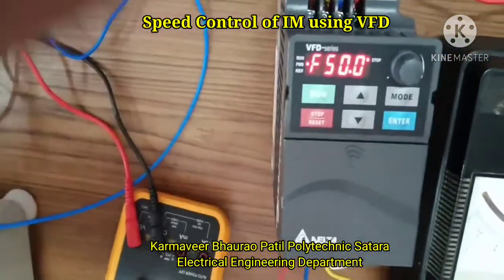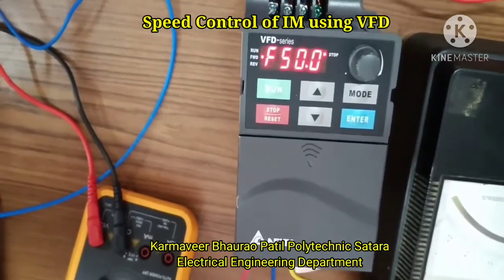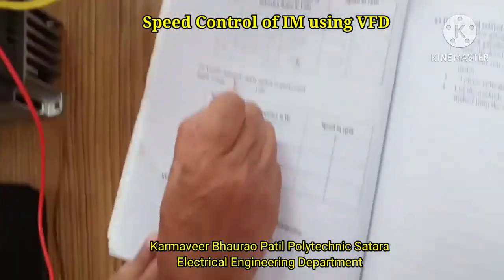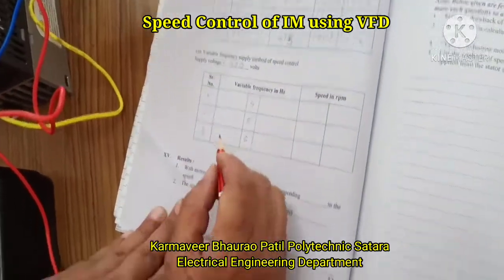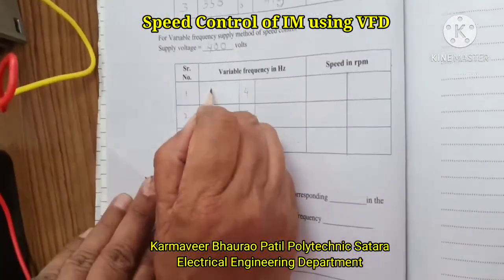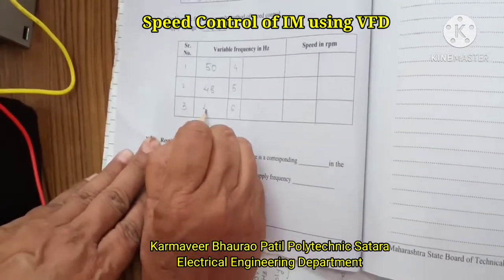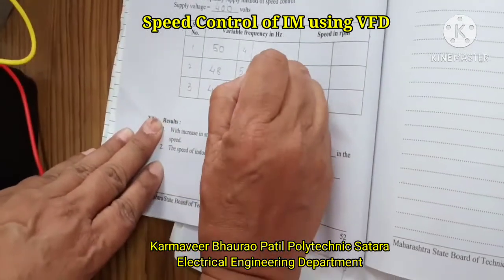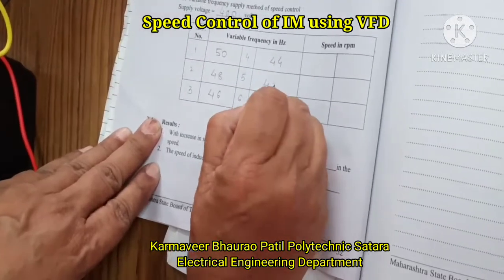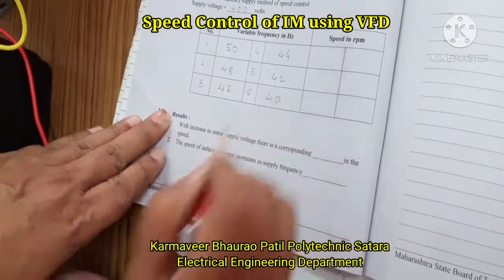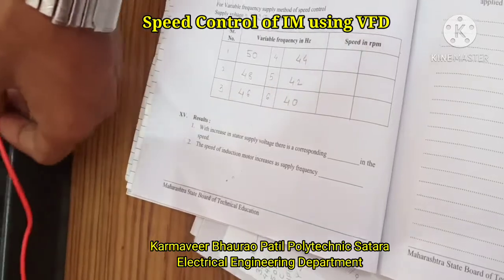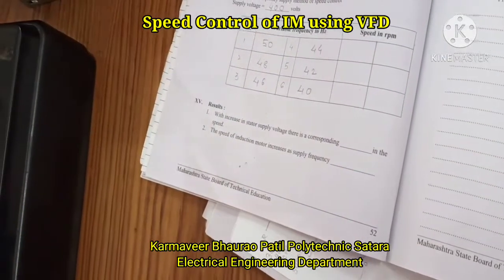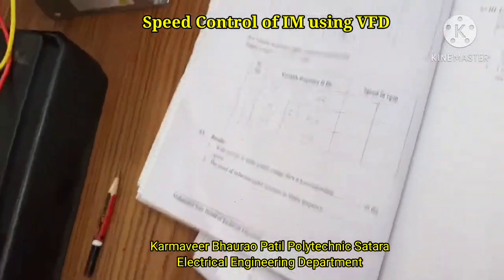Once you have adjusted the voltage, you will have to note down the supply voltage as 400 volts. Now what is the frequency? We are going to adjust it to 50 hertz, then 48 hertz, 46, 44, 42 and 40 hertz. So that way we are going to change the frequency. Till the time we press the switch on the VFD drive, the motor will not be started. We are given the supply.